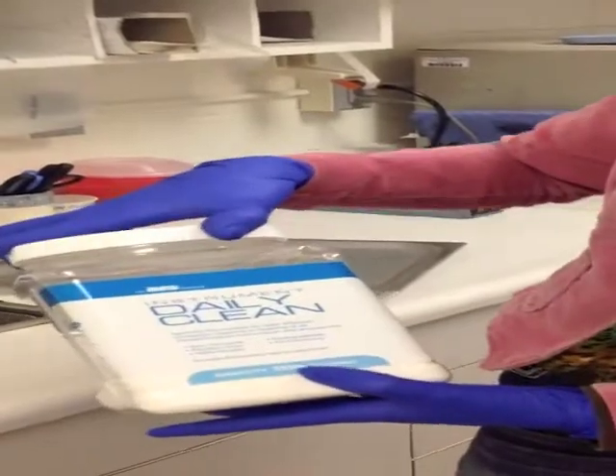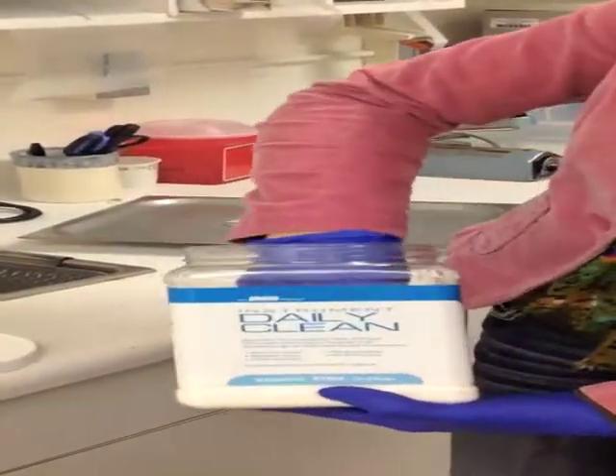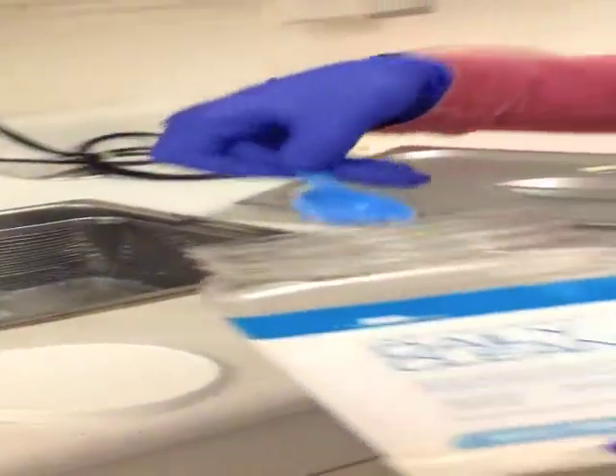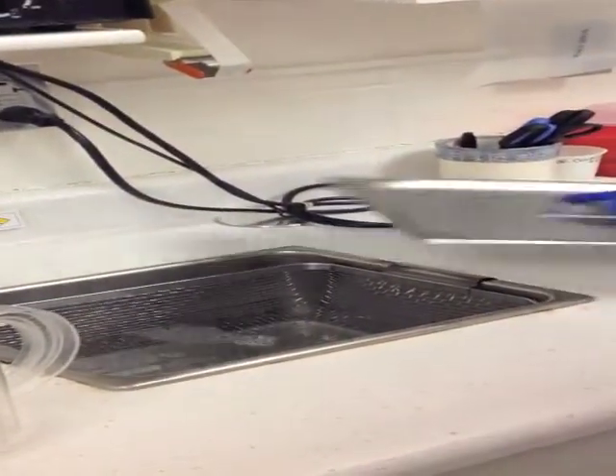Once it's full, you're going to use the Daily Clean crystals that can also be found under the sink, and you're going to use 3 level scoops and place it into the water. If you forget how many scoops you should need when mixing the solution, all of the information can be found here above the ultrasonic, and it tells us exactly what we need. Once this is full, it is then ready to be used for instrument cleaning.